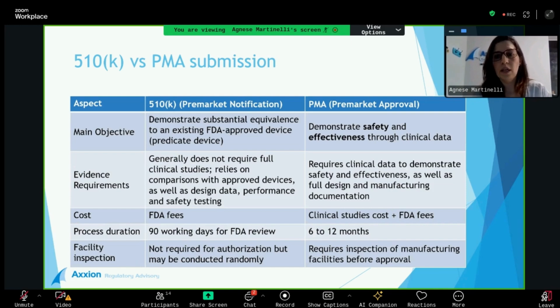The evidence required in the PMA is much more complex in order to demonstrate the safety and effectiveness we mentioned, and we must also address the full design and manufacturing documentation. In the 510K, in general, it relies only on the comparison with approved devices, as well as on the design data and performance and safety testing. Regarding the cost, in both submissions we have FDA fees, but we must also consider the clinical study cost in the case of the PMA, which is rather expensive. So it's something to take into account.